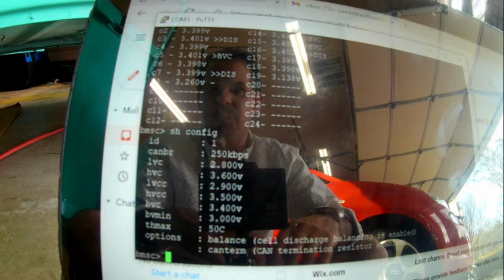Balanced voltage cutoff, BVC, means when the voltage of any cell is above 3.4 volts, the BMS sends a signal to our charge controller to lower the current to a trickle charge, which just maintains the battery against parasitic losses. BVmin is the minimum floor of 3.0 volts, at which the BMS will try to balance the pack by draining the cell with the highest charge. As long as the voltage is above 3 volts, it will attempt to do this.